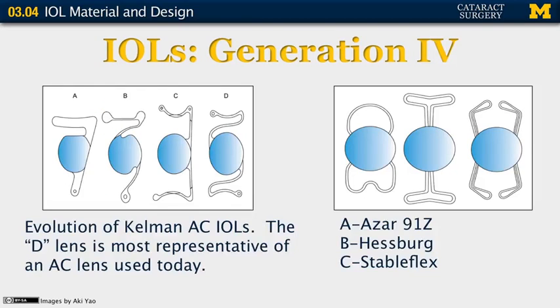The fourth generation of lenses are shown here with many examples of anterior chamber lens implants. The lenses on the left are examples of Kelman anterior chamber lens implants, and you will note that lens D is very similar to the modern anterior chamber lens. All of these are open loop haptics so that the haptics are quite flexible, and this flexibility allows the lenses to be very well tolerated in the anterior chamber. Lenses on the right are other versions of anterior chamber lens implants that were briefly in use. These lenses all have closed loop haptics, and they were all associated with corneal endothelial failure and issues with chronic inflammation.